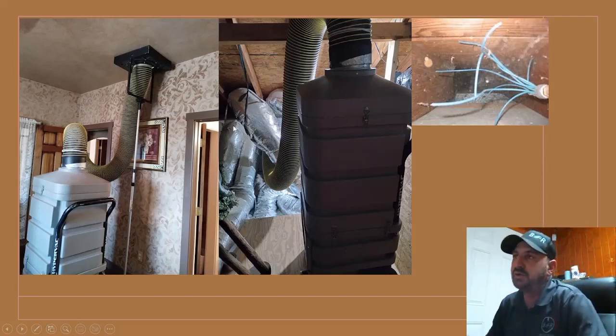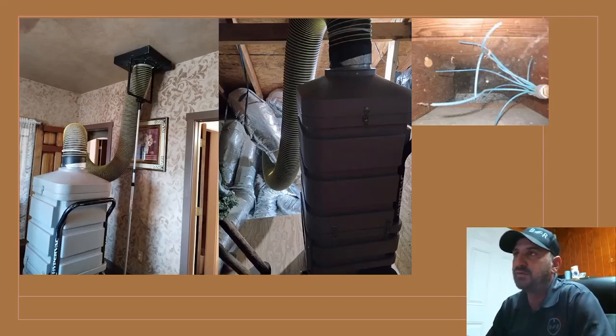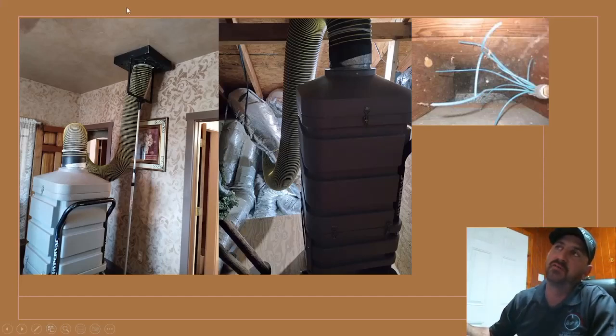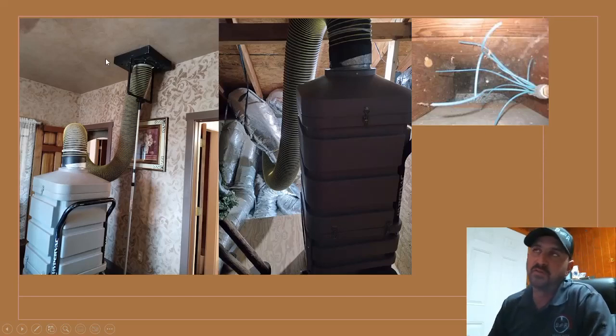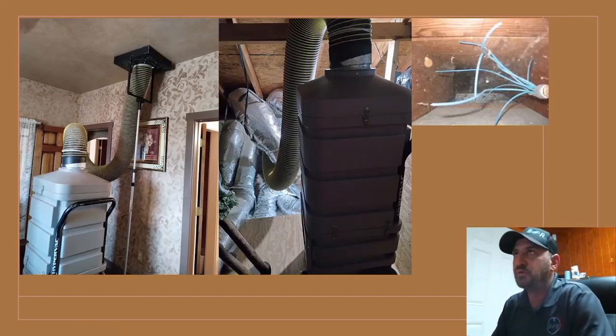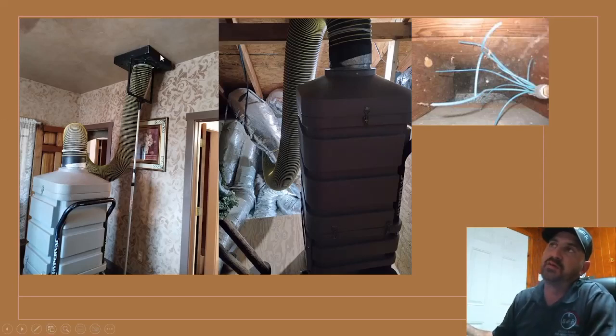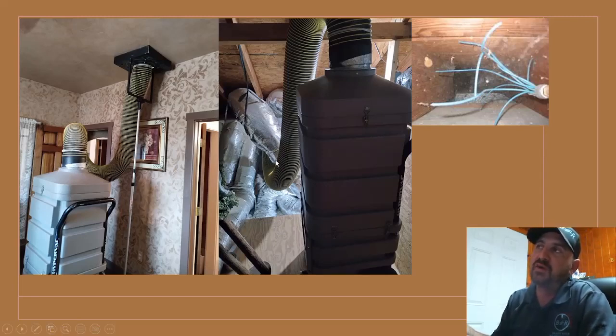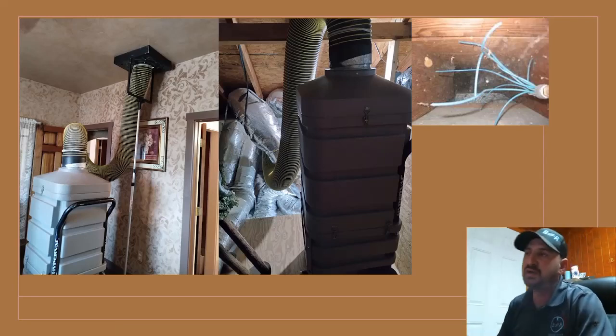One thing they did really well, that I'm sure not everyone does, is to do this properly they take all the grills off so they can cover them up with bags or cardboard, and then hook up to the other end of the duct system, covering a supply or return. Basically they're sucking through that system, but all the grills are covered so it creates a good vacuum.